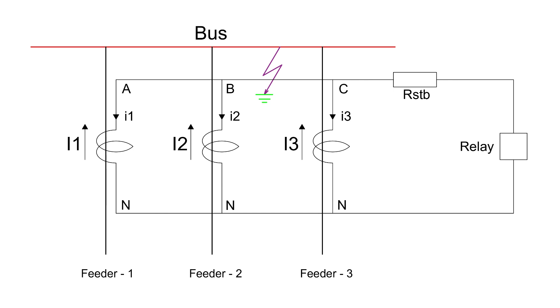If there is a fault on the bus, according to Kirchhoff's current law, the summation of current will not be zero, resulting in a net current flowing through the relay coil, causing it to operate. However, under normal conditions, the summation of the current is zero, meaning no current flows through the relay coil, keeping the relay stable.